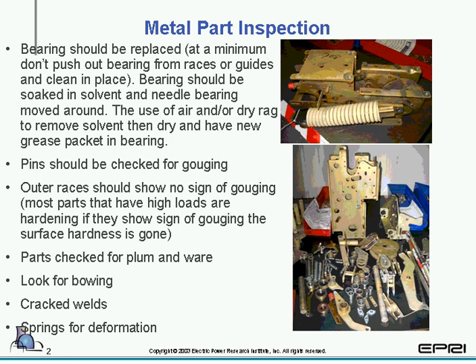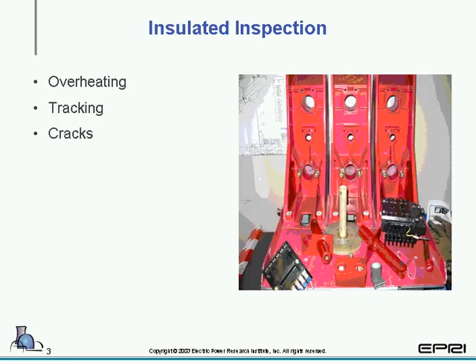Bearings, as spoken about. If you're not replacing the bearings, you do not want to remove them from the guides. Most overhauls will replace bearings. And then check for cracked welds, deformed parts, and when you're doing your inspection on your parts, do not assume that the part is correct just because the breaker was functioning.